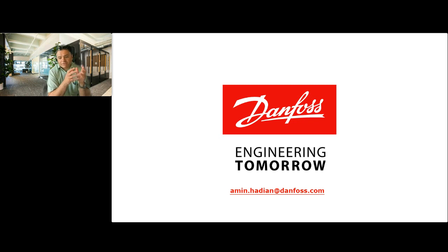The other way is that if you, for example, have your laptop open and you are sitting outdoors and suddenly it starts raining, you will never have any impact or explosion, because the water cannot bring that kind of electrical shortcuts or whatever. So it's not damaging your equipment. The second thing is that whenever you have a fire inside those data centers, you are not bringing the water everywhere within that room. You are just trying to bring the water or the water mist only around the area where you have the server on fire, and not the other areas, because all the other nozzle heads are closed. Whereas if you have an extinguishing system with gas, you have to bring the whole gas at the same time into the whole room.